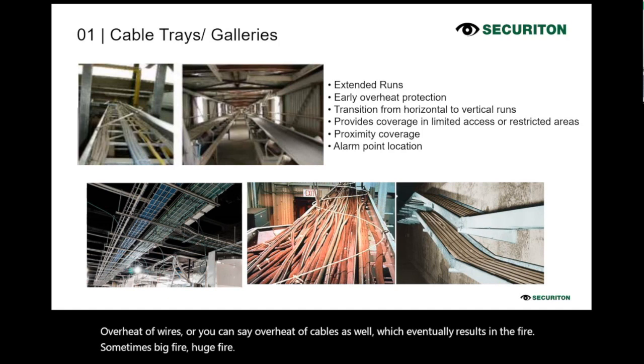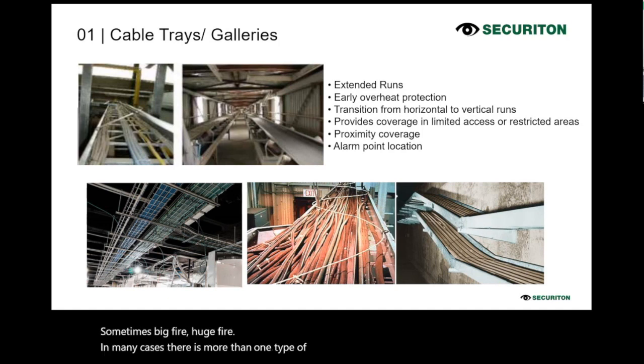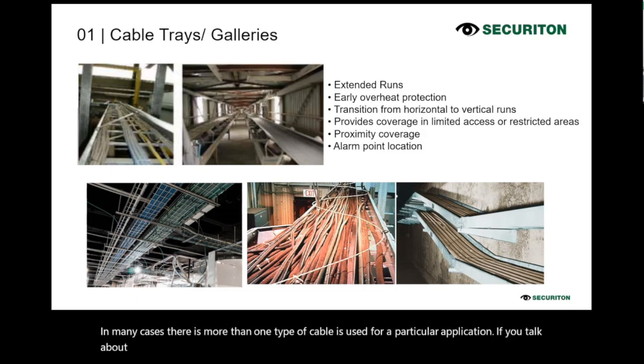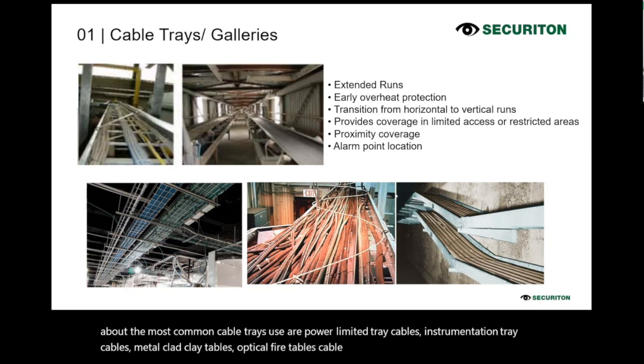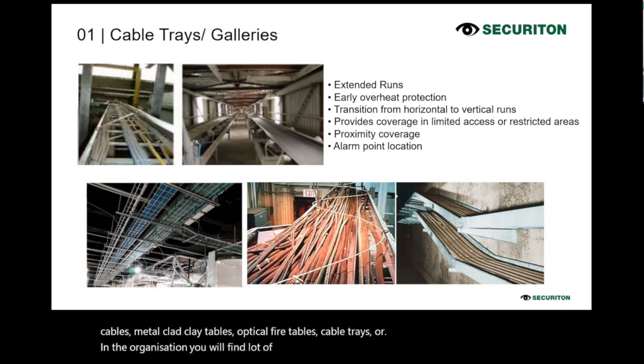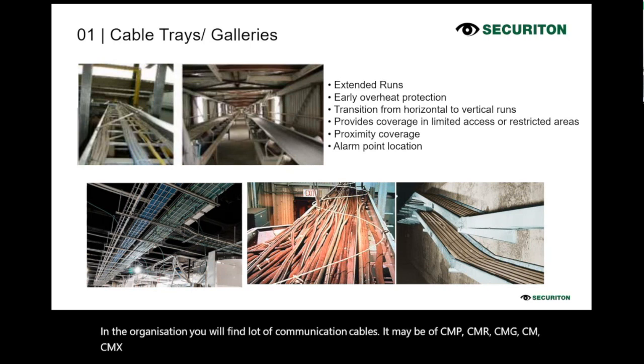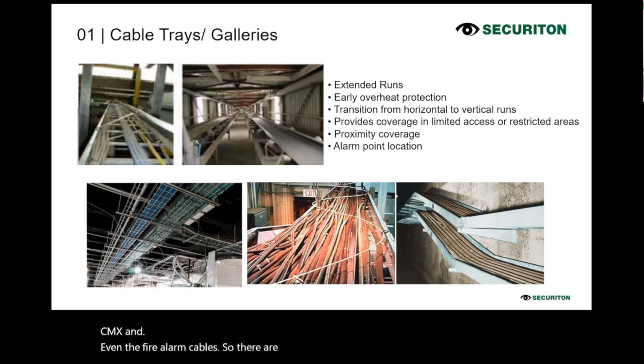In many cases, more than one type of cable is used for a particular application. The most common cables used are power limited tray cables, instrumentation tray cables, metal clad cables, optical fiber cables, and in the organization you will find a lot of communication cables. They may be of CMP, CMR, CMG, CM, CMX, and even the fire alarm cables. So there are chances of fire because of these cables.